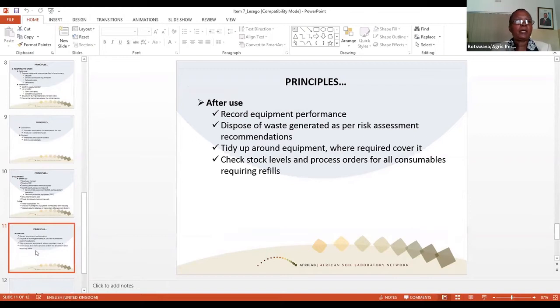After use, we have to make sure that we record what we have observed during the operation. Is the machine calling for maintenance? Is there any deterioration? Sometimes if your plan says every 3 months I'll do the maintenance, you might find that the workload says otherwise.